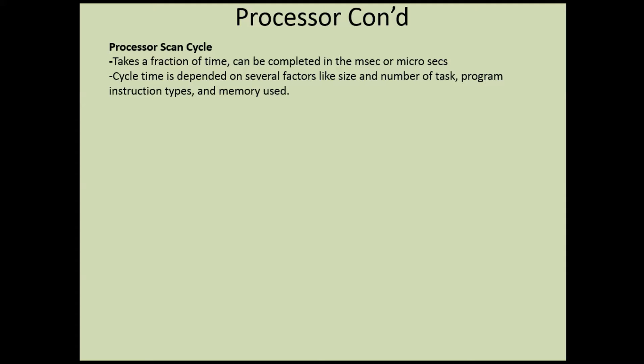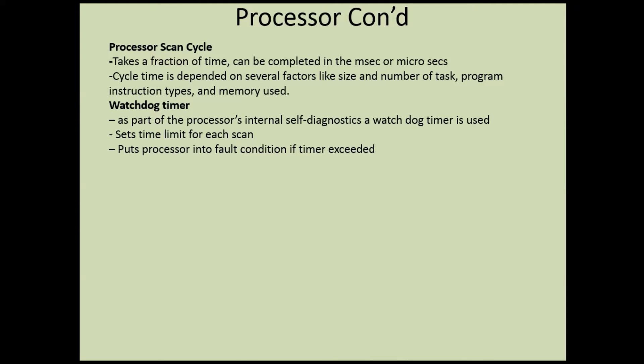The processor scan cycle takes a fraction of time and can complete in a millisecond or microseconds - it's getting faster and faster. Cycle time is dependent on several factors like the size and number of tasks, program instruction type, and memory used. Just like a computer, the more memory and tasks it has to run through, the slower it gets. Also incorporated is a watchdog timer as part of the processor's internal self-diagnostics. It sets a time limit for each scan, and if a scan takes longer than expected, it will put the processor into a fault condition.